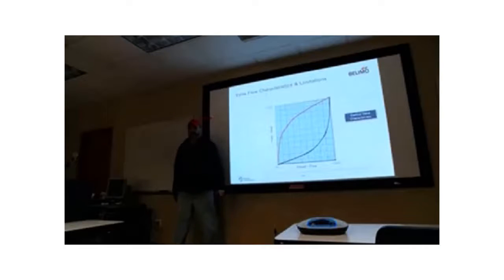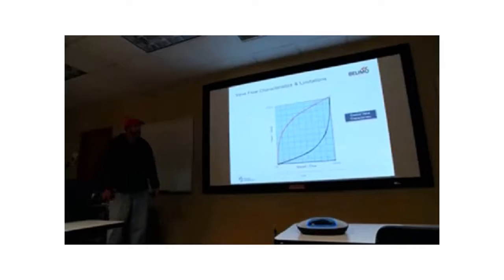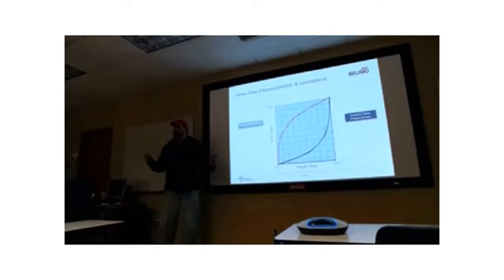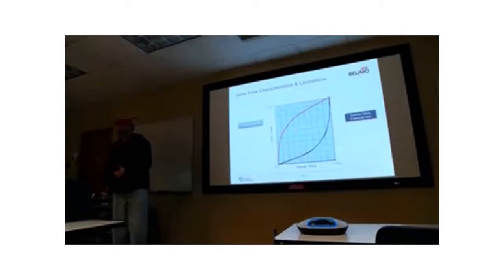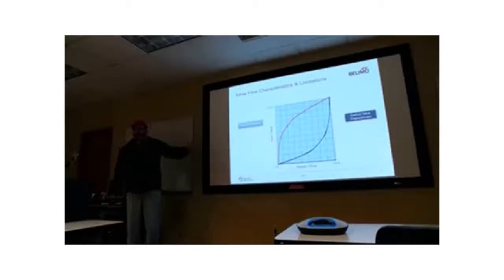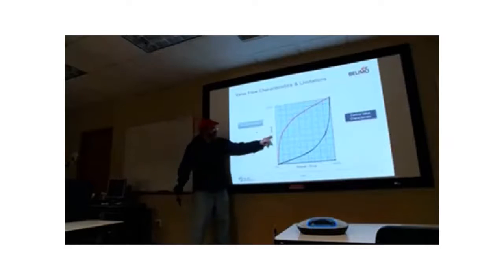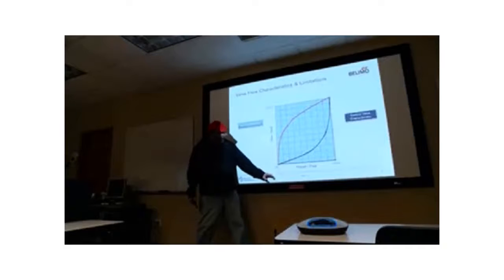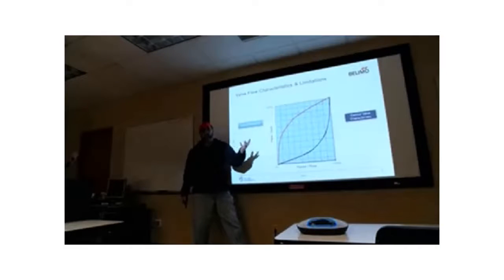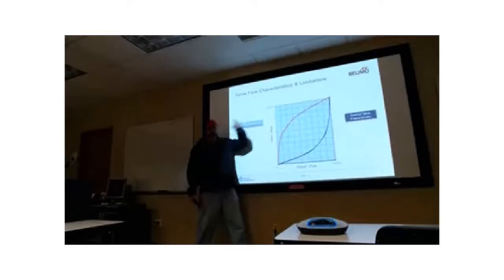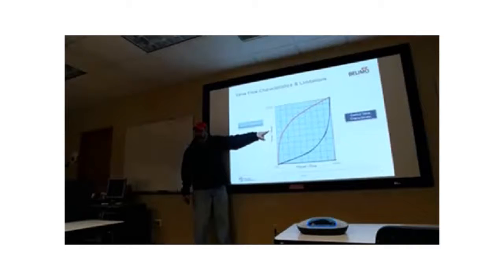What do you think this one is? Your BTUs or your heat. It's the coil, right? Because remember, what are we controlling? We're controlling flow through the coil. Right? And why do we put water through the coil? To get heat transfer, right? You either want a chilled water coil or a heating water coil. It doesn't really matter in this case, but with the coil characteristic, what happens is now we have on this horizontal axis the flow rate, right, the water flow rate in gallons per minute. But on this axis, as Seth said, we've got heat transfer, BTUs per hour.